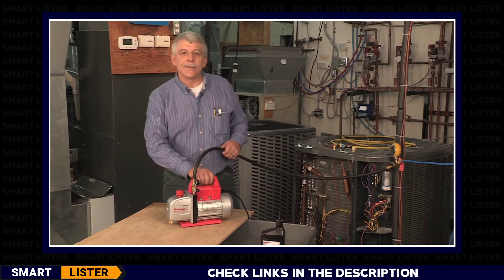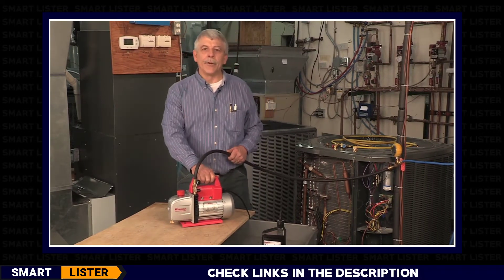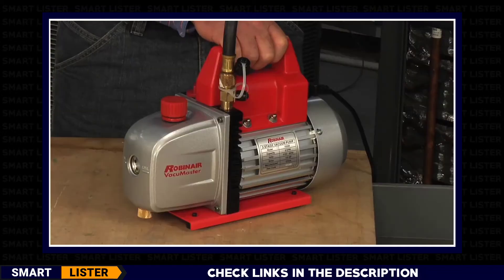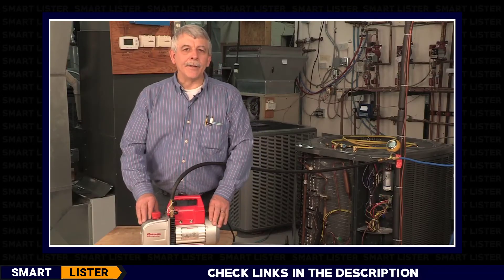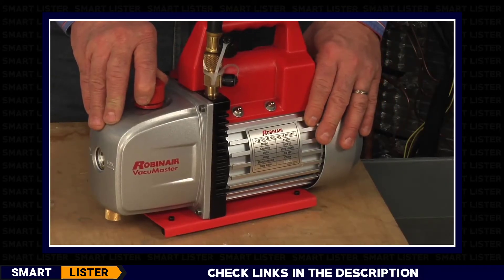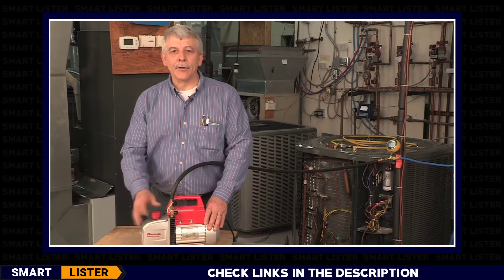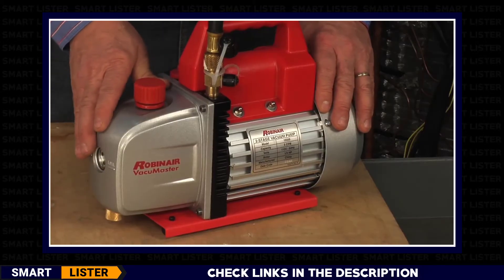The two-stage design removes air and moisture from the system quicker and more thoroughly, leading to a deeper ultimate vacuum level. The heavy-duty one-third horsepower motor features a rotary vane, steel bearing, high-torque design for easy startup and efficient operation. The new cast aluminum reservoir design reduces weight and creates a strong, durable pump.